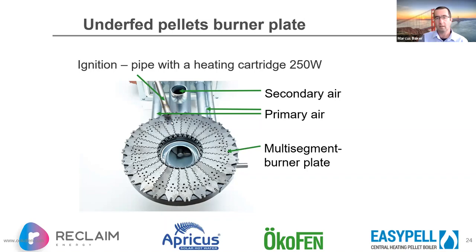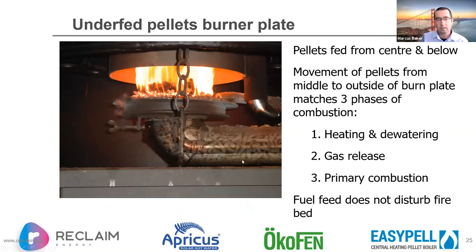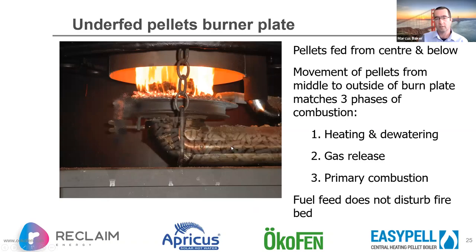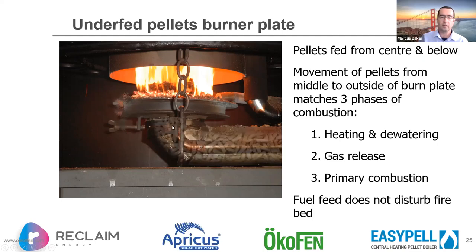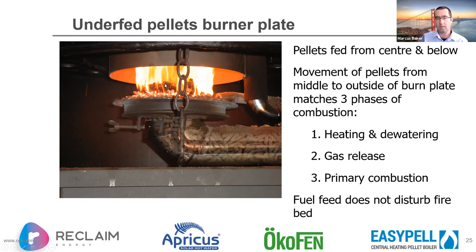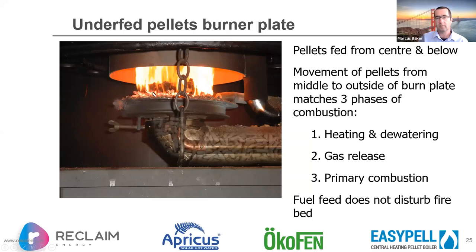You can see the ignition cartridge — a small electric igniter with forced air producing a jet of very hot air using only 250 watts. Because air is blown over it continuously, there are no overheating issues. Primary and secondary air comes up through tubes, and the whole rear assembly is essentially an air box. In the animation you can see pellets being forced through the pipe, pushing up and moving from the centre outwards — the underfed grate principle.